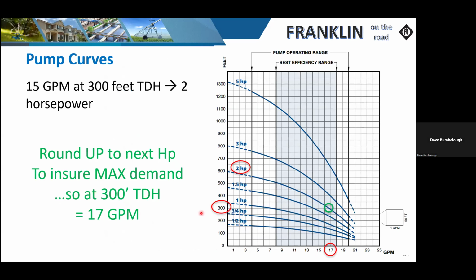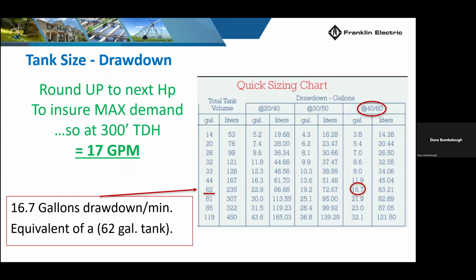So if we go to 300, we come across and intersect that 15. It's not quite a 1.5 horse, but if we step it up to 2 horsepower, we can clearly achieve that. Now granted, we're going to get about 17 gallons per minute on that particular TDH number. So I can use that if I absolutely needed to make sure I had 15 gallons per minute going to the home. Now, here comes the dilemma.